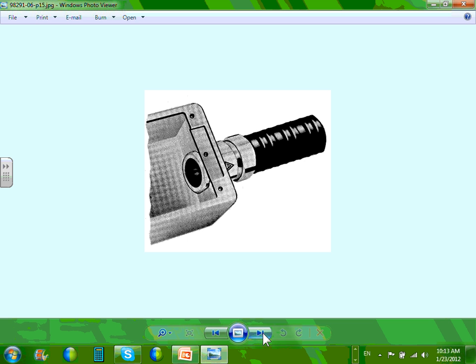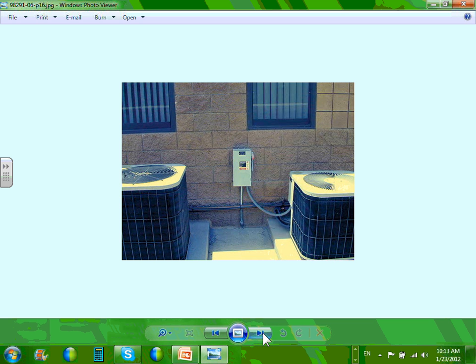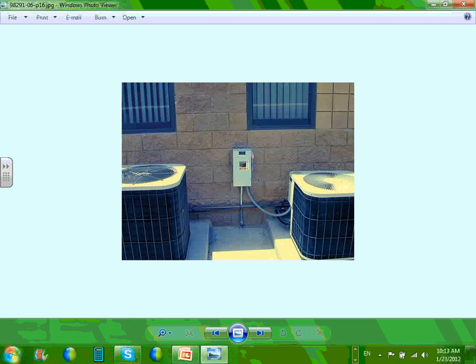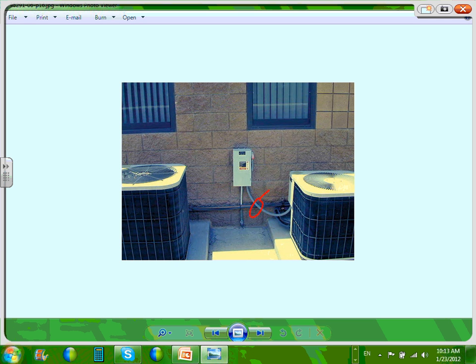Stub-ups and back-to-back connections, guys. Here's what I thought was a good example of where to use liquid tight flexible metallic conduit. This is the typical example of how to use liquid tight flexible metallic conduit to tie to equipment. You'll see that a trillion times, guys. In the past, you used to be able to use flexible metallic conduit here. Now you have to use liquid tight flexible metallic conduit from the disconnect to the disconnected equipment, 100 times. This could be on the roof, could be anywhere in a wet location.